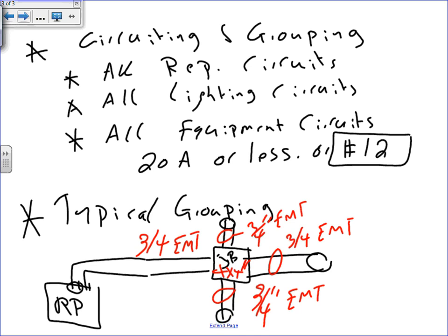So now we know the typical conduit they're going to use. Now, can I take an inch? Yeah, you can. When would I take an inch conduit? An inch, in my book, is when you're going to an air handling unit, a dedicated load. 2 inch for a big chiller that needs conductor size 2 inch, a dedicated load. Does that make sense?